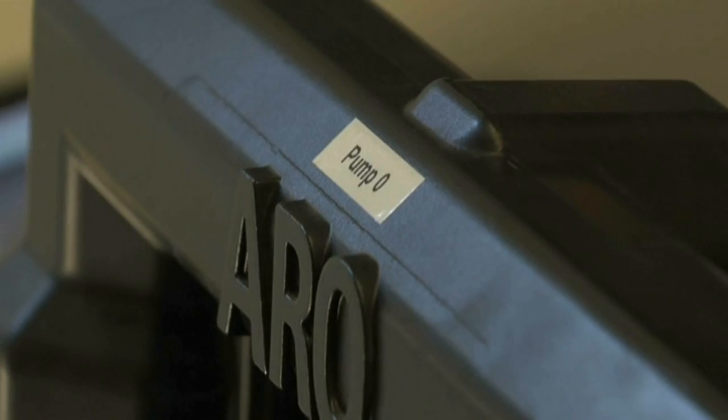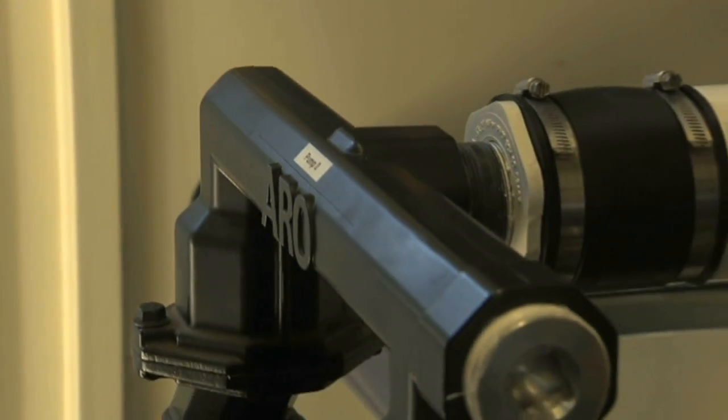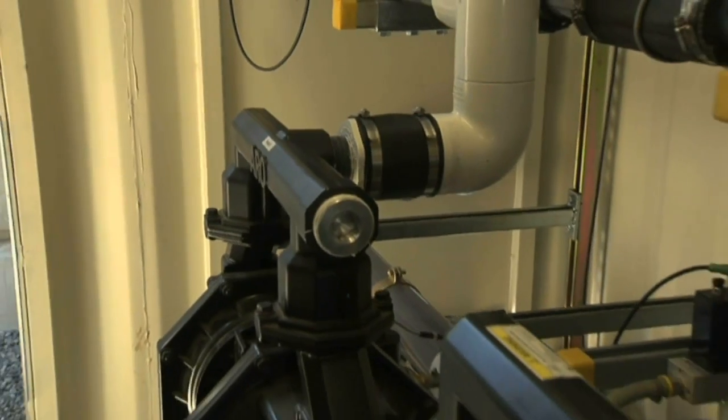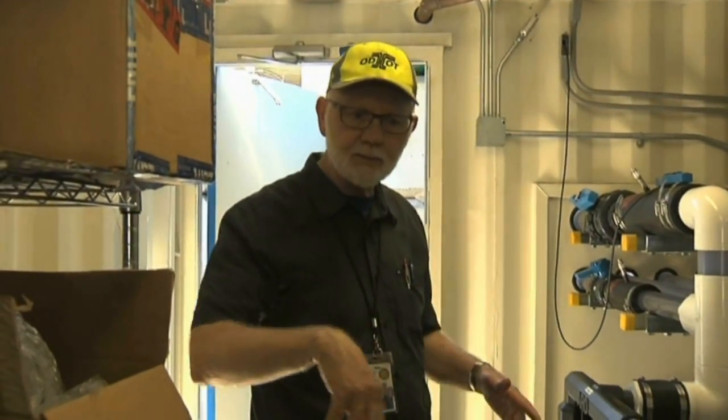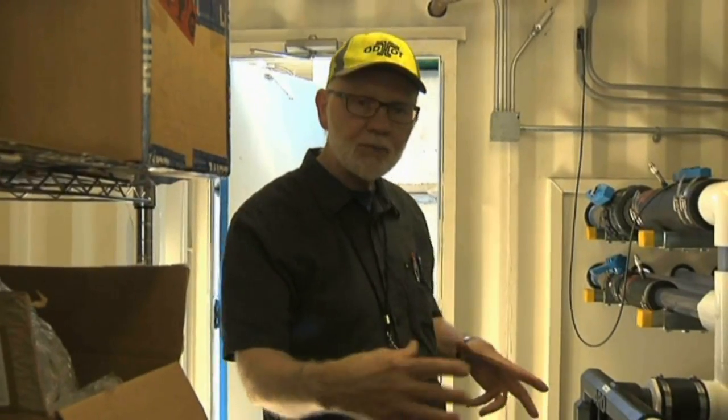You're looking at pump zero. We called it zero because it doesn't send water to a stormwater technology. Instead, it pumps water back to the wet well and stirs the contents to make sure that the sand goes to the middle of the manhole, and the other three pumps then pull that sand out and send it on to the technology that's being tested. That way, any sand that has come along the big 84-inch pipe will go all the way through our system and get out to the technology that needs to remove that sand material.